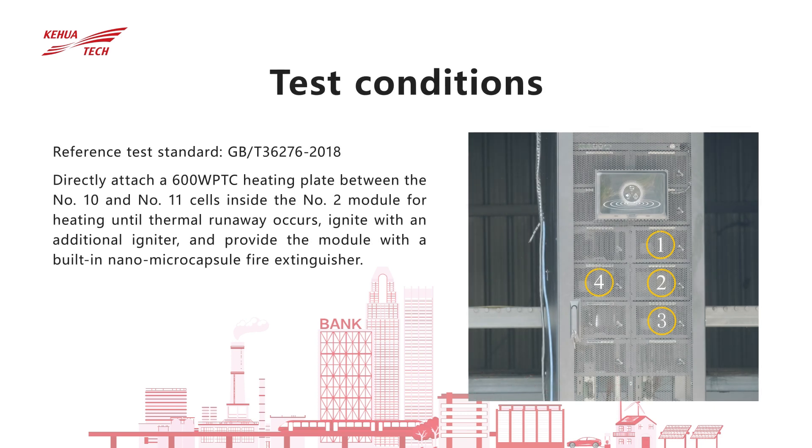According to the test method in GB/T36276-2018, directly heat a 600-watt PTC heating plate in the middle of number 10 and number 11 cells in the number 2 module battery pack until thermal runaway occurs.